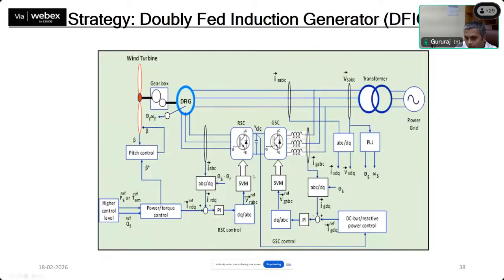Wherein what they actually do is connect a series transformer, and to the other side of the series transformer they connect an inverter. So the idea is very simple. If the root cause of all the problem is the dip in the voltage, this transformer and DVR arrangement, basically the inverter control, would sense the amount of dip in the voltage at the point of common coupling, which is closely connected to the doubly-fed induction generator, and it will try to compensate by injecting the voltage that is dropped because of the fault, so that you're trying to solve the problem at the root end itself.